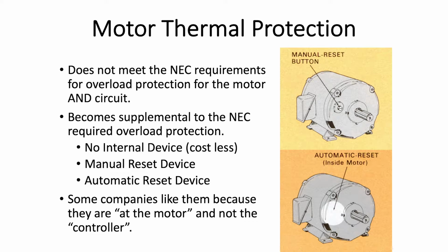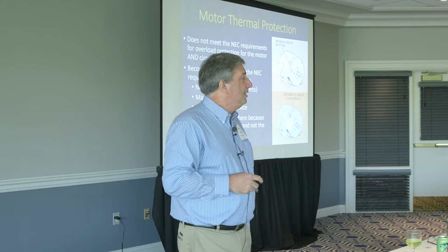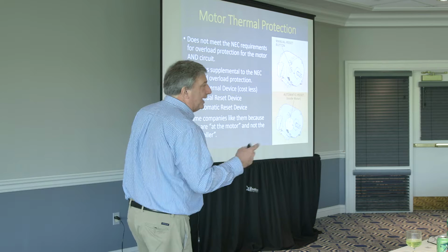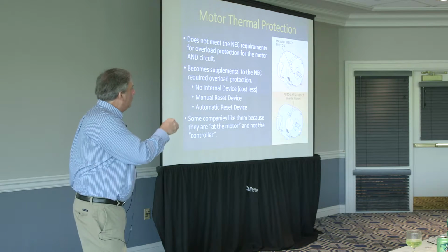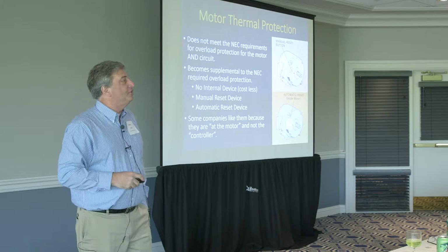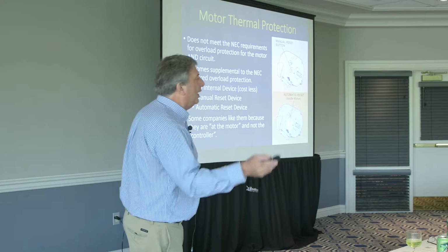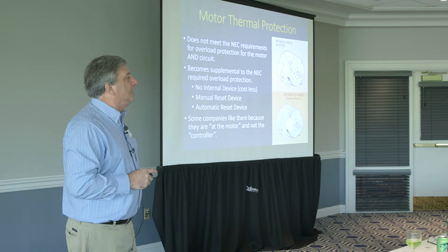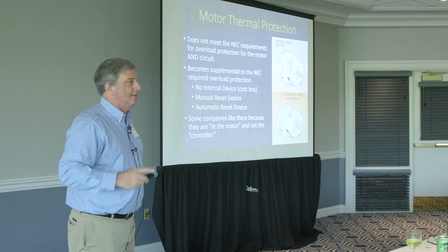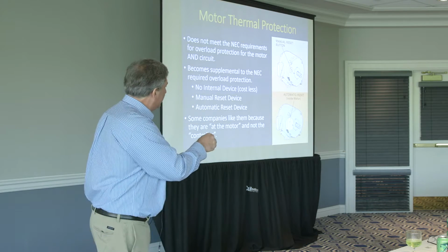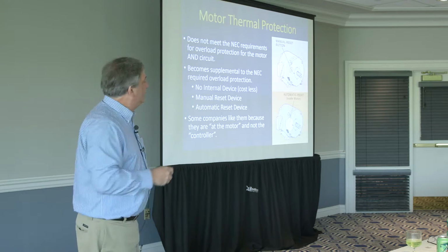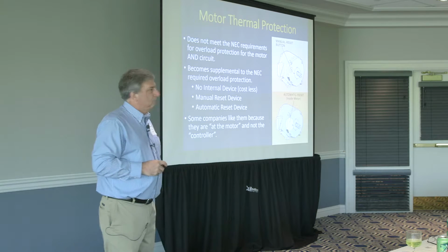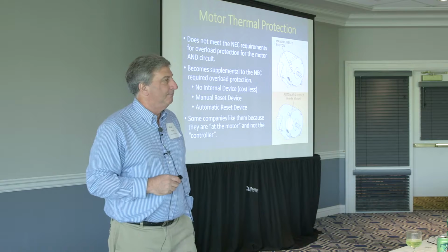So I can buy motors that have an internal overload device. And motors that have an internal overload device can have a manual reset overload or an automatic reset overload. And the idea in the National Electric Code, which is safety, is we don't care about that device. It's optional or supplemental. We care about the one in the starter panel that we're going to use in terms of all of our safety things as the primary. Fine, you want to do that, you can put that in there. But the ones in my starter panel, okay, those are not going to be automatic reset.